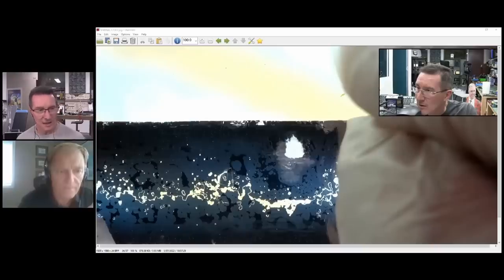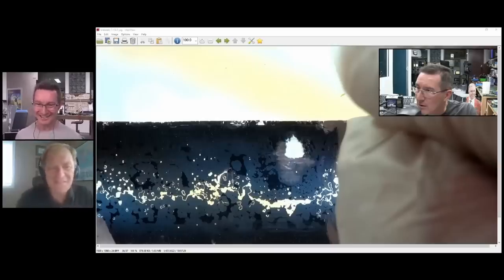So this large hole here, I don't think that's a self-healing blowhole, would it? Would you get one that large? Well, you could. It depends what hits it. I think that's maybe more unlikely. Maybe I've torn it there. Is it possible that I've torn this when I've taken it apart? Yeah, I think he did a good job on the DPA, but I think we might have approached it a little bit differently. Right, okay. Well, it was my first time. Oh, you did good. We'd still hire you.